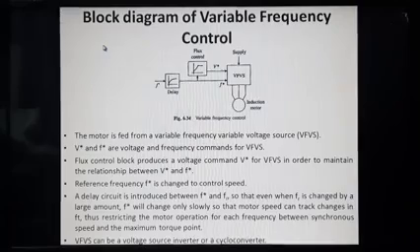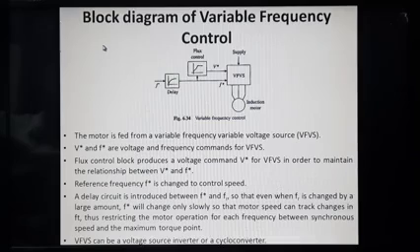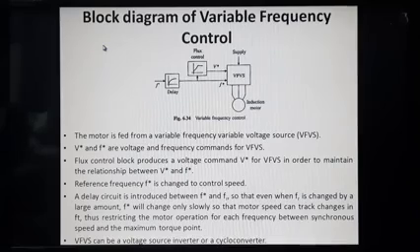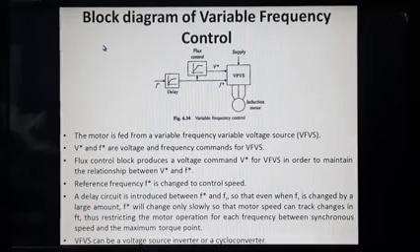What happens is, already the machine is running at 1500 rpm. So the machine won't be able to step the speed from 1500 rpm to 60 rpm suddenly. What this delay circuit will be doing is changing the value of frequency gradually, from the rated frequency to the frequency corresponding to 60 rpm.